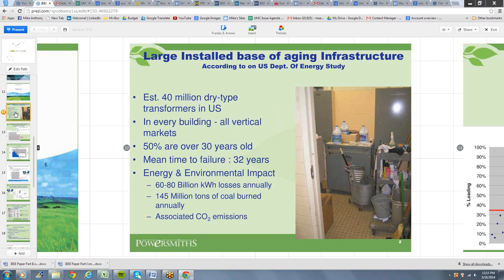for the application. In terms of energy and environmental impact, we're talking about pretty big numbers, summed across the country: 60 to 80 billion kilowatt hours of losses. So there's dollars, obviously, and grid capacity tied up with those. About 145 million tons of coal need to be burned to feed just the transformer losses. So there are pollution and CO2 footprint consequences. So the transformer is not something to be ignored.